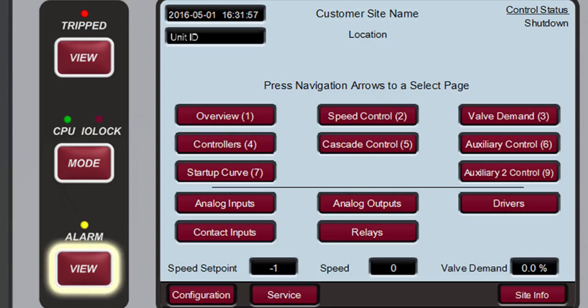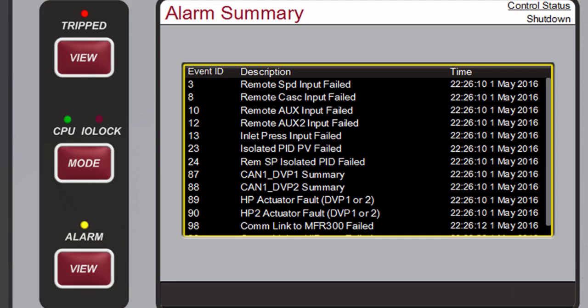Pressing Alarm View opens the Alarm Summary screen. When an alarm is detected, it gets latched in the event logic. The alarm relay is energized, and the alarm LED illuminates yellow. The cause of the event will be indicated with an event ID, description, and time and date stamp. The list will always place the first alarm condition to occur at the top of the list. The most recent alarm condition to occur will always be placed at the bottom of the list.